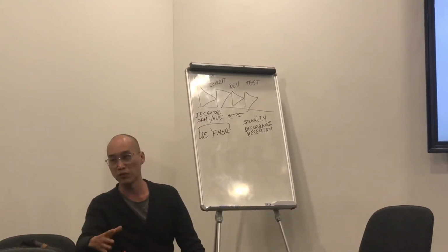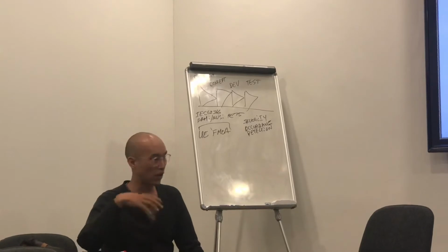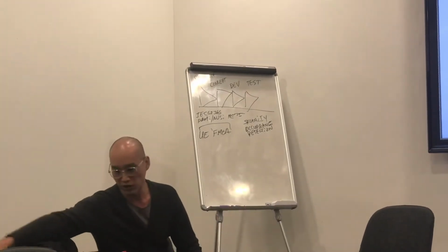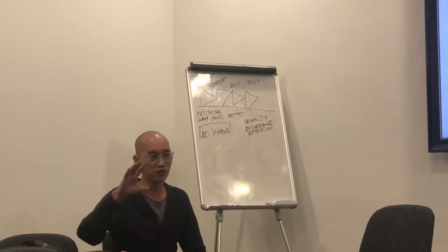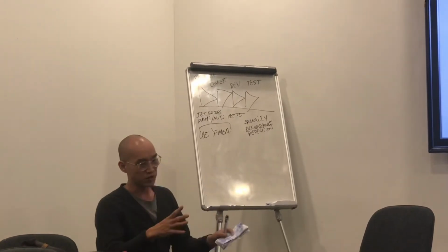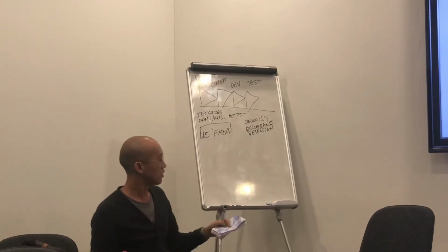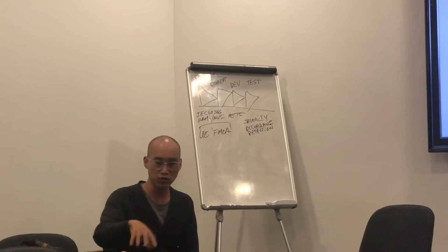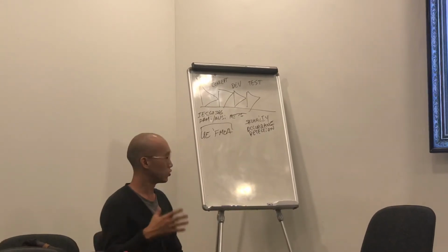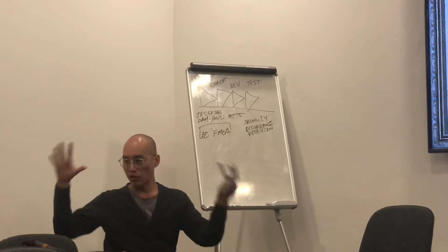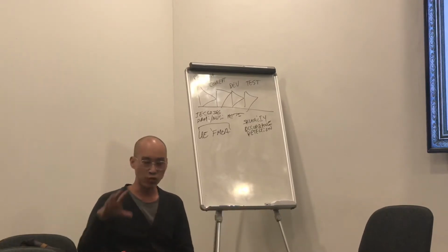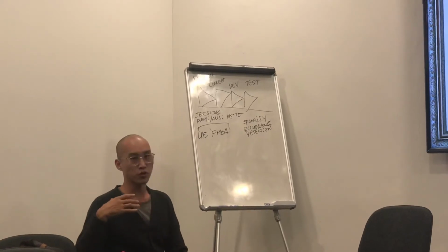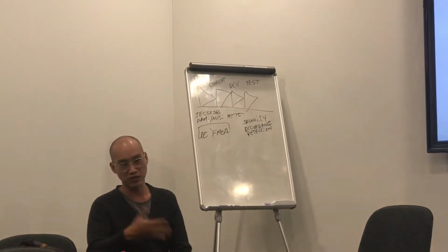In the example last week we were talking about medical products and how as engineers and designers and researchers, when we were working on the project, we had to spend a significant amount of time doing research to understand how this product could go wrong, how it could be manufactured wrong, how the user could use it wrong, in order to make a mind map, an understanding of where the risk is. And then that will tell us where we should put our effort as a design team, as an engineering team.